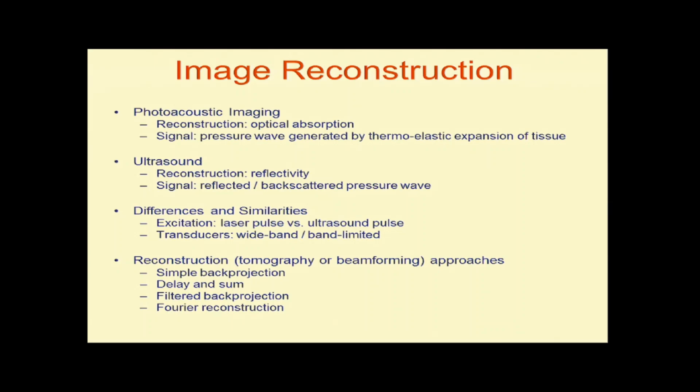Right, there are differences and similarities, and I can give you at least 65 publications on this topic if you're interested in reading them. But let me tell you that probably these four are the most commonly used reconstruction techniques: simple back projection and filtered back projection, that's CT language; delay-and-sum would be the language of ultrasound reconstruction; and Fourier reconstruction, more of optics. All of them are somewhat similar and have little niches where they perform better in one case than the other.